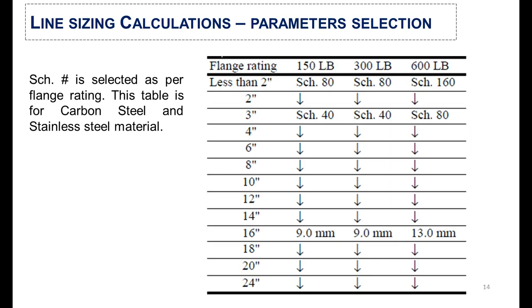The schedule number is selected based on the flange rating. This table shows the flange rating and schedule number for stainless steel and carbon steel materials. For example, if the flange rating is 150 pound and the line size is less than 2 inches, the schedule number will be 80. Similarly, for flange ratings of 300 pound and 600 pound, the schedule number is found according to the line size.